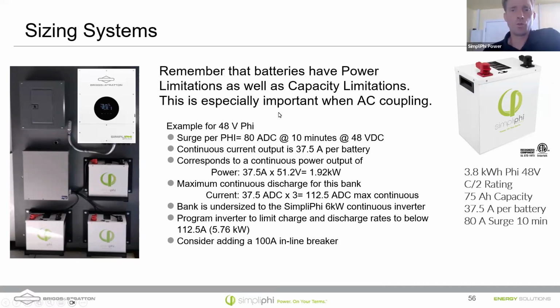Okay, so just want to let you know, it is important to size your systems appropriately. The batteries all have power ratings, right, in addition to storage capacity ratings. So a battery that's 75 amp hours, if we're discharging that over 2 hours, would be 37.5 amps per battery, right? And so that 37.5 amps times the nominal voltage tells us that each of these, the Phi and the AmpliPHI battery, can provide about 1.9 kilowatts each.